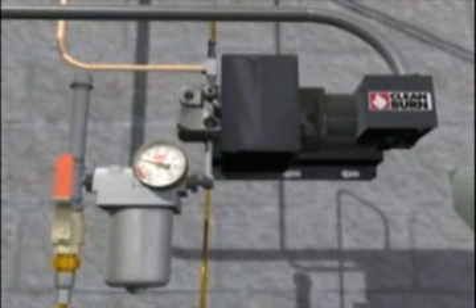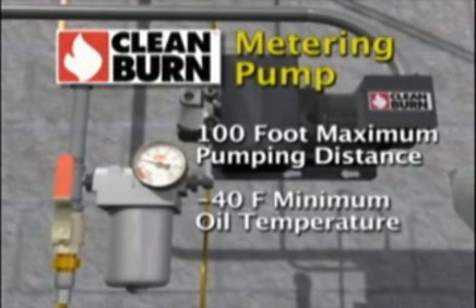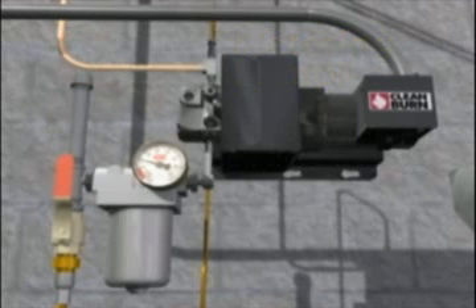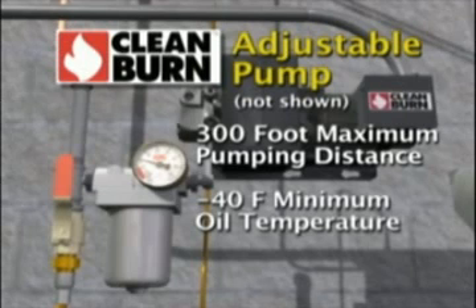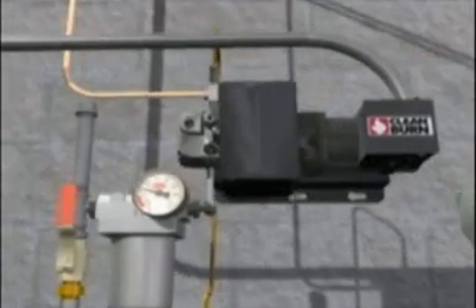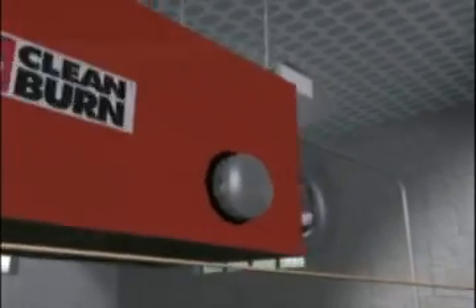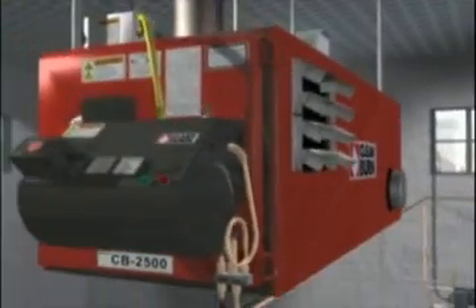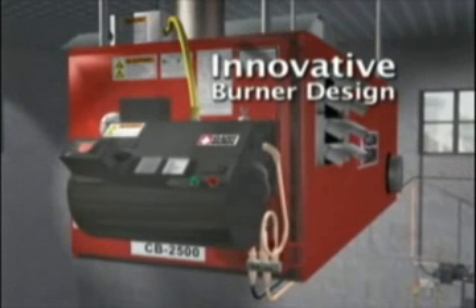CleanBurn's brawny, reliable metering pump, shown in this video, allows the furnace to be installed up to 100 feet from a storage tank. It also permits the use of an outside storage tank where, in colder temperatures, many competitive pumps cannot function. In addition, CleanBurn offers an adjustable pumping system that can handle oil line runs up to 300 feet in length. No competing waste oil furnace can provide such flexibility and convenience. The oil line, along with an air line, feed into CleanBurn's innovative burner.